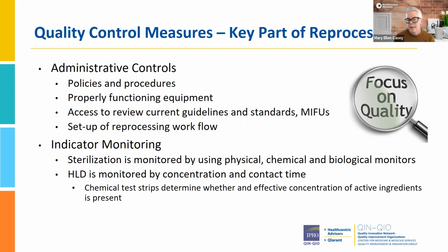And if you do reprocess, that you set up a good workflow where there are established clean and dirty areas. One of the other things to think of is what kind of equipment you need to support your reprocessing efforts. With indicator monitoring, you need the equipment to do it, whether it's sterilization or high-level disinfection, having those monitors in place to make sure that it's safe and effective.